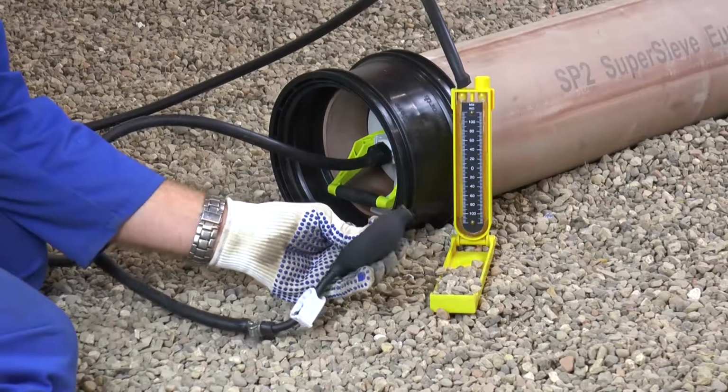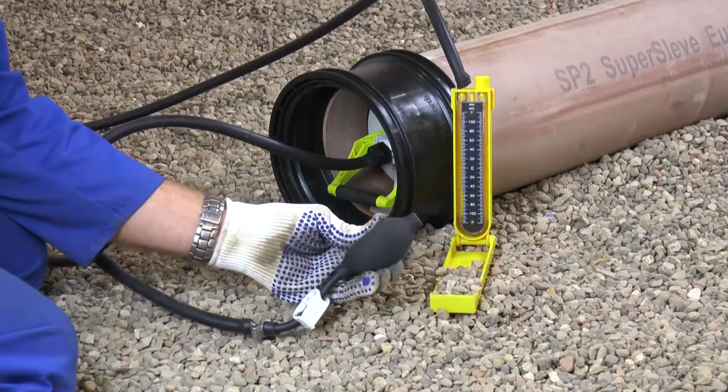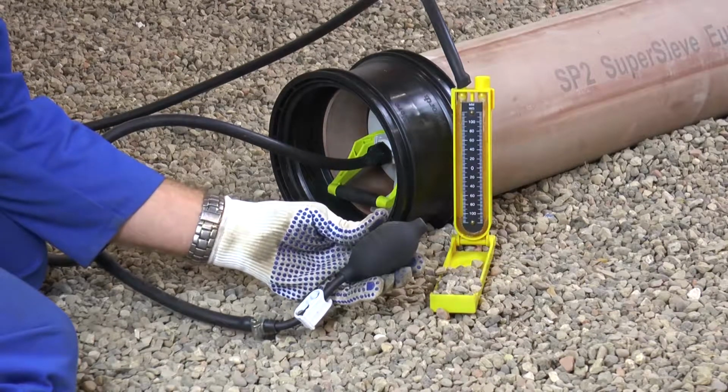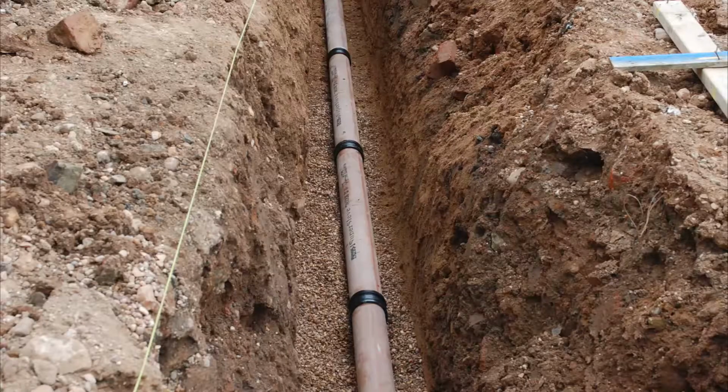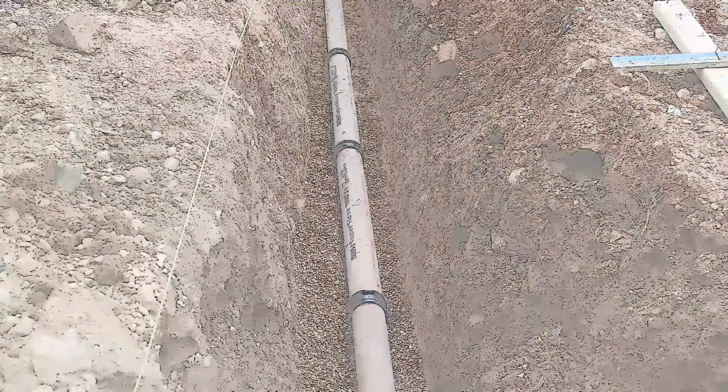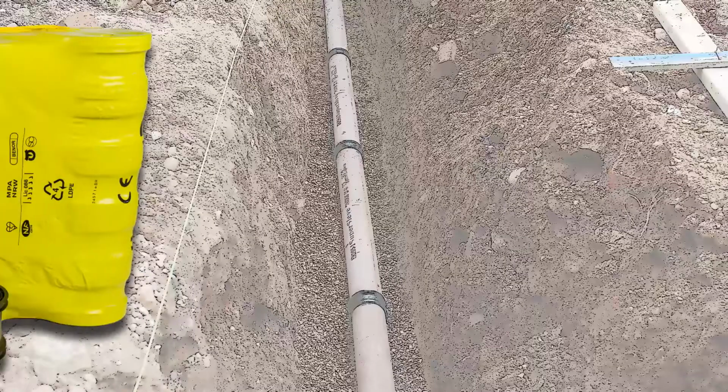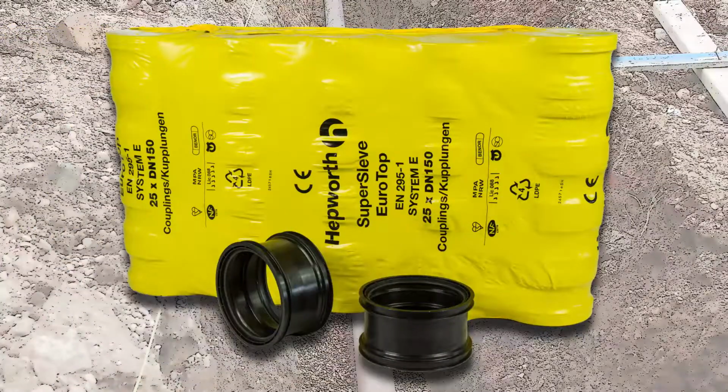It is recommended that you only install a few pipes before applying a quick intermediate air test check, so that you do not have to remove too many pipes to get back to the point in the system where the pipeline will hold a test. Checking that pipeline jointing has been done correctly as you go. Replace any defective couplings if found, and remove them from the work area so that they can't be reused.